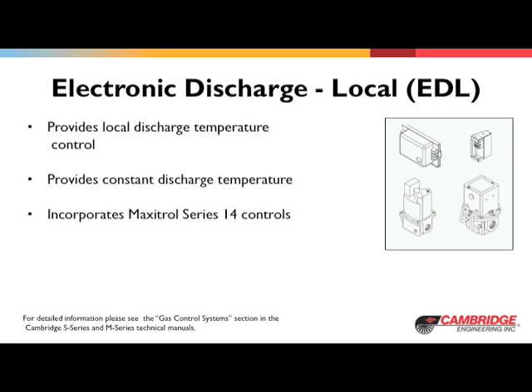The EDL incorporates Maxitrol 14 series controls. The components utilized on the EDL are an A1014R1 amplifier, a TS114J discharge temperature sensor, and either an MR212, an M511, or M611 modulating valve.